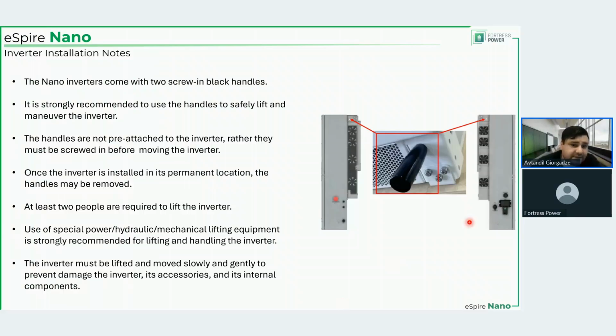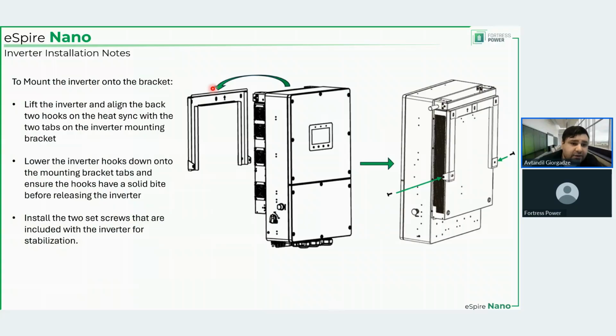And coming from the weight, if you are not using special lifting equipment, at least 2 people should be handling this. Please don't try doing it alone. It's very heavy. It's 200 pounds. Then, how we put it onto the bracket. So once the bracket is secured, it has sort of a lip on the top, and you put the inverter on top of the bracket, and then it kind of hangs onto the bracket on this lip, and then you use the fastening screws on the sides, 2 of them, to permanently secure the inverter there. That way, even if someone tries to lift it, the screws will not allow anyone to do that while they're there. And also, this lip that I was talking about here will not turn into an axis of rotation for the inverter if these screws are holding the inverter in place.